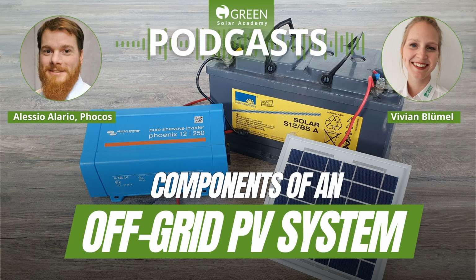The AC or DC coupling always refers to how your PV is connected to your battery, essentially. With AC coupled, again, it's a grid inverter via AC through an off-grid inverter into the battery. So there's a few conversions happening there. And a DC coupled system tends to be PV through some kind of a charge controller directly to the battery. You could theoretically have an AC coupled system and simply run your loads off the battery in DC. You could theoretically do that. Yeah, but nobody really does. I don't think I've ever heard of a system like that. No, it would be weird.